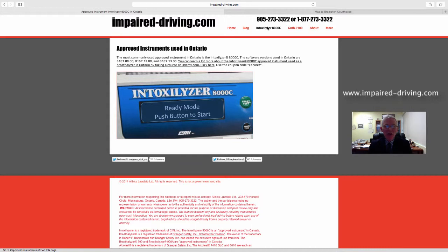Lawyers need to understand that there are several potential problems with infrared-based instruments if they are not used properly and maintained properly. Because these instruments quantify alcohol in breath and multiply by 2100 to 1, they have to obtain and use deep lung air. If the calculation is based on stomach alcohol or mouth alcohol or a burp or a belch or vomit, then the sample is not suitable, the sample is not being obtained properly, and the calculation, the analysis, will not be reliable.